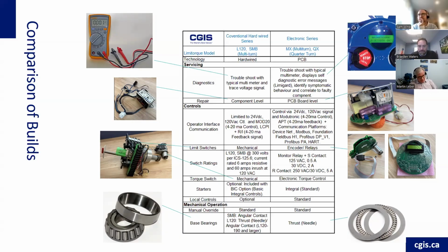There's features in there that you can get feedback, 4 to 20 milliamp signal feedback. The electronic series has that also, but in addition, you can get it with special communication boards such as DeviceNet, Modbus Foundation, HART, where you can communicate not only through the 24 or 120 volt signals, but through these other platforms.